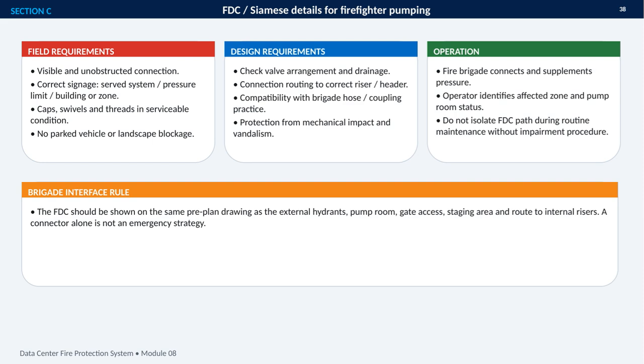From a design standpoint, the arrangement should include appropriate check valves and drainage, and the connection must route to the correct riser or header. It also needs to be compatible with brigade hose and coupling practices, while being protected from impact and vandalism. During operation, the fire brigade connects to supplement system pressure. The operator identifies the affected zone and confirms the pump room status. The FDC path must not be isolated during routine maintenance unless the proper impairment procedure is followed.